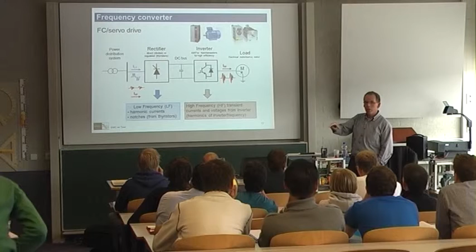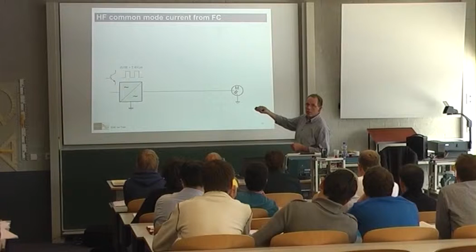So the dV/dt, the steepness of the voltage as a function of time, is well around 3 kV per microsecond. That's actually what you buy in terms of semiconductors. That's what you can get on the market. And of course, the faster you have this switching, the less dissipation you will get in the transistors. So the keyword in the last decades actually was high efficiency rather than EMC. So we had lots of problems in industry because of these motor drives. Because we used very steep voltage switch mode power supplies, and then with this capacitance you get this common mode current. And of course we use some screening.